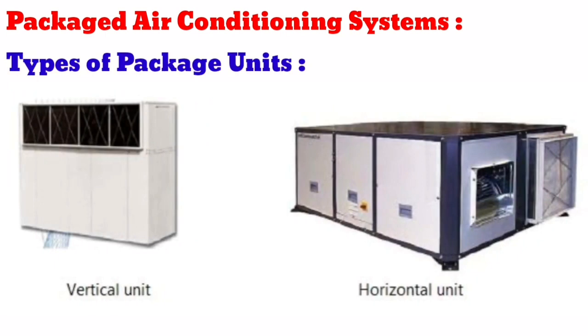The evaporator and condenser are kept together in one package, delivering conditioned air directly into a room or duct work. Three main types of package units are distinguished by their mounting and blowing capability: vertical package, horizontal package, and rooftop. Vertical package units blow air horizontally or vertically upwards — the lower section contains the compressor, condenser, and condenser fan, while the upper section contains the cooling coil and blower. Horizontal package units blow air horizontally, with typical cooling capacity ranging between 3 and 20 tons.